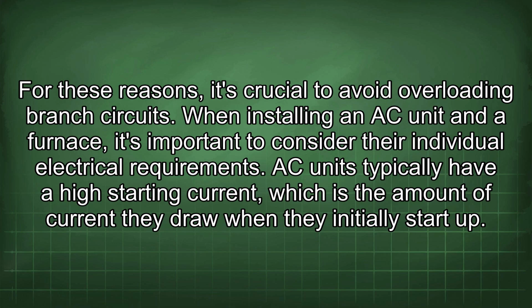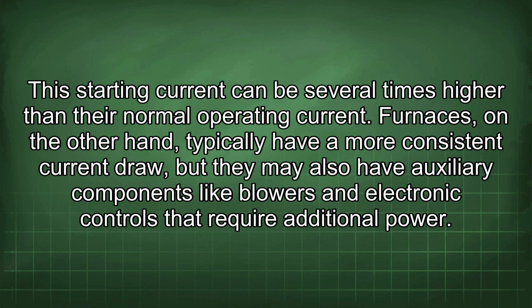When installing an AC unit and a furnace, it's important to consider their individual electrical requirements. AC units typically have a high starting current, which is the amount of current they draw when they initially start up. This starting current can be several times higher than their normal operating current. Furnaces, on the other hand, typically have a more consistent current draw, but they may also have auxiliary components like blowers and electronic controls that require additional power.